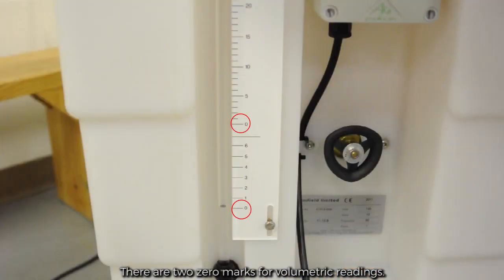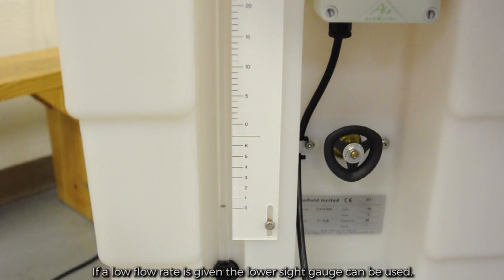There are two zero marks for volumetric readings. If a low flow rate is given, the lower sight gauge can be used. To know if it can be used, your time collection of volume must fall below six liters before the given time requirement.